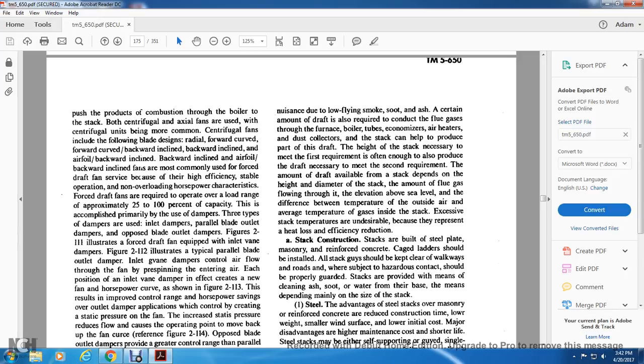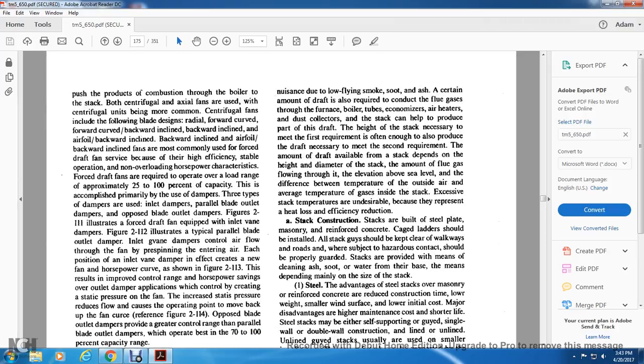Three types of dampers are used: inlet dampers, parallel blade outlet dampers, and opposed blade outlet dampers. Figure 211 illustrates the forced draft fan equipped with an inlet vane. Figure 212 illustrates the typical parallel blade outlet damper. Inlet vane dampers control airflow through the fan by pre-spinning the entering air. Each position of the inlet vane damper effectively creates a new fan horsepower curve, as shown in figure 2-113.